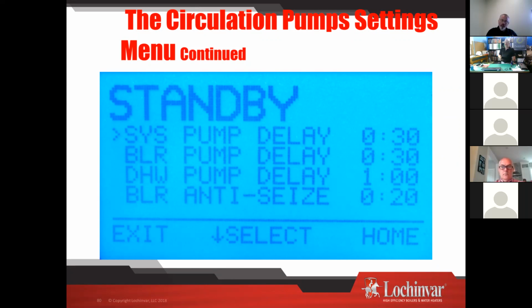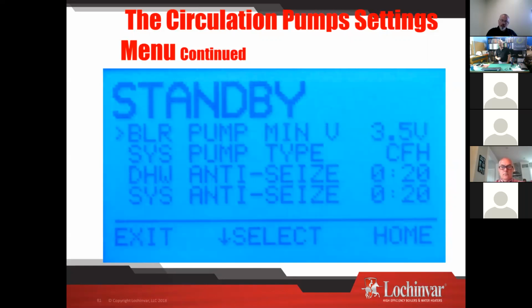Anti-seize: if the pump goes 24 hours without a call, it's going to turn on and run automatically. Way back in the original, back in 2005, they put that in there, and you couldn't adjust it, so they didn't tell anybody. They didn't market it. Then every once in a while a customer would call and say, my pumps are running. You'd say, no, you must be crazy, because your pumps aren't running. And you could never catch it. And then finally it was like, oh yeah, it is, because every day it cycles those pumps through. So it's kind of cool.